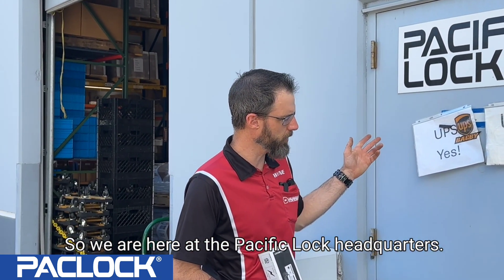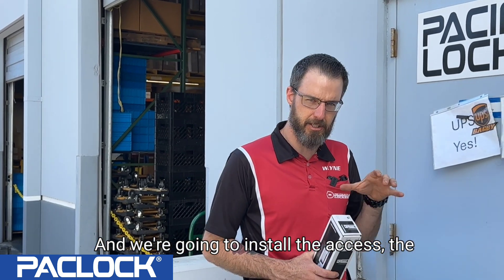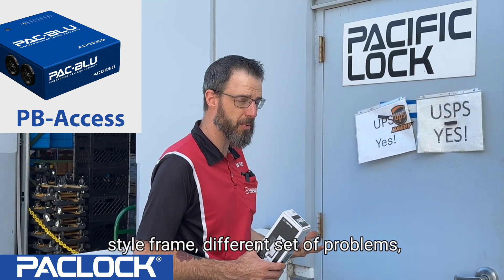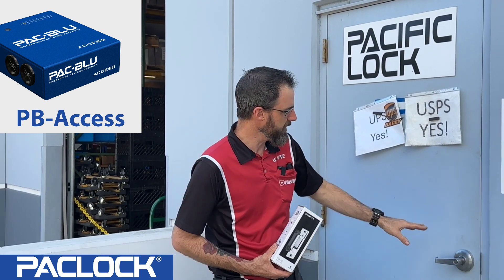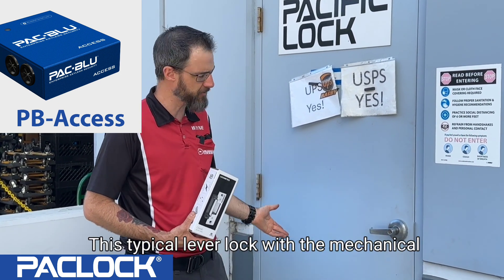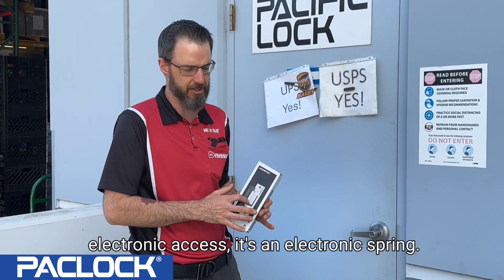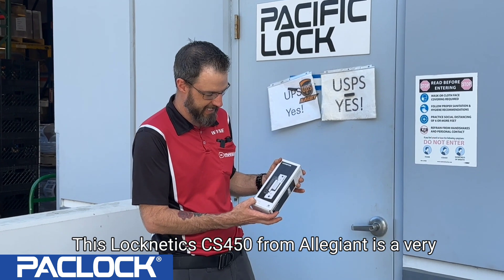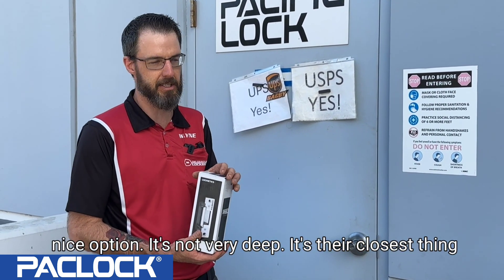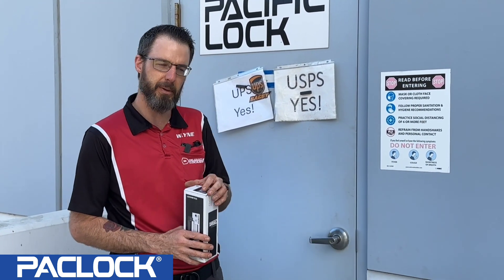We are here at the Pacific Lock headquarters — this is their back door — and we're going to install electronic access on this door as well. We have a different style door, different style frame, and a different set of challenges to overcome. This cylindrical lever set is a typical lever block with a mechanical key override. The easiest way to add electronic access is with the Allegion CS450 electronic strike, which is a nice, low-profile 'no cut' option, though you do still need to modify this area slightly to get it in there.